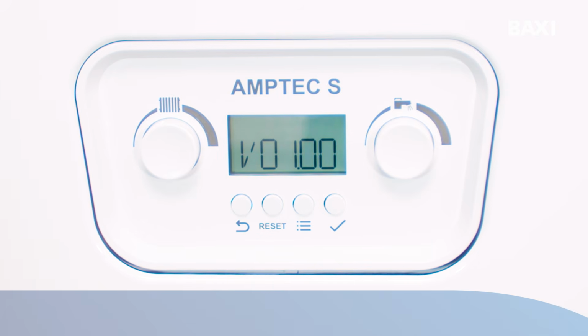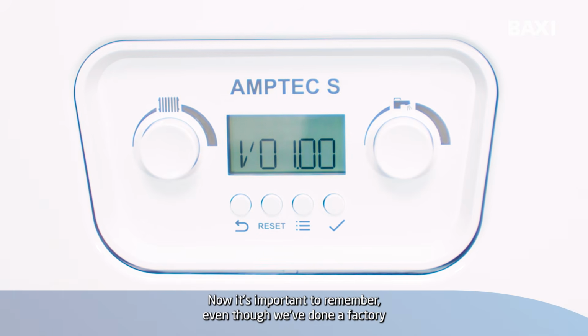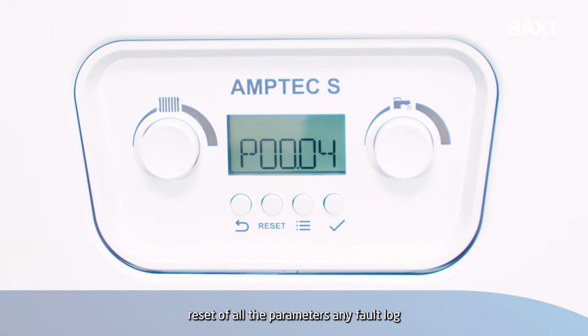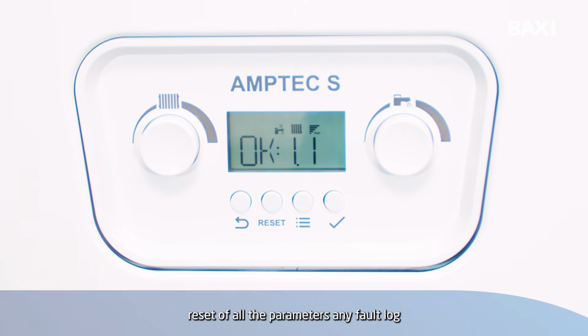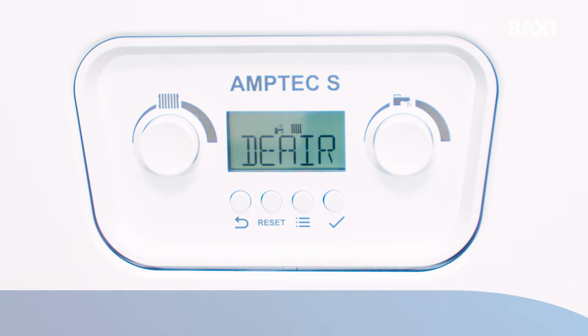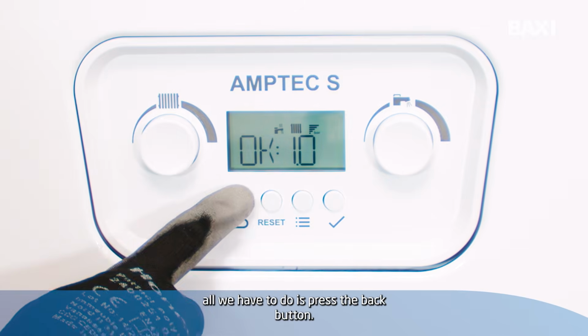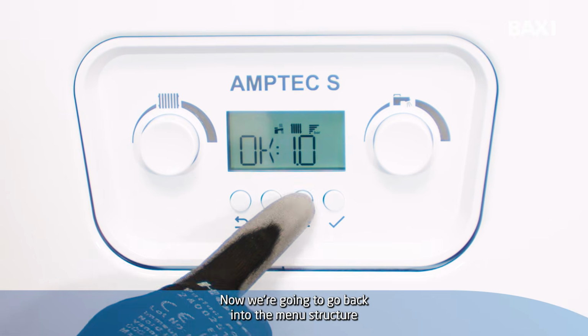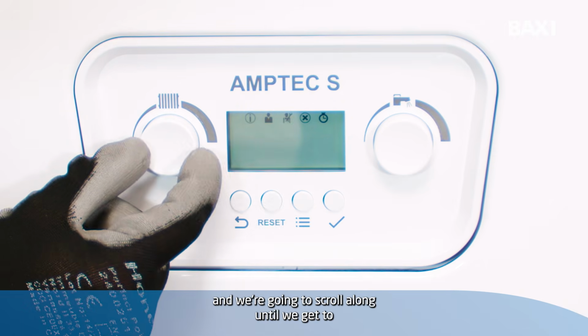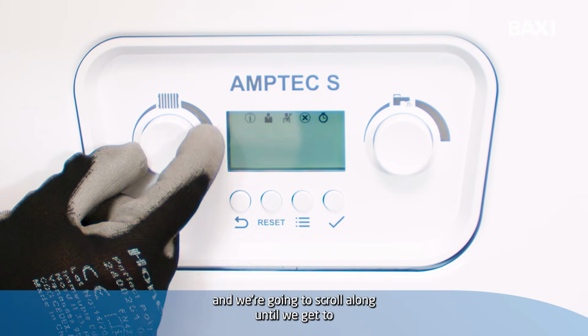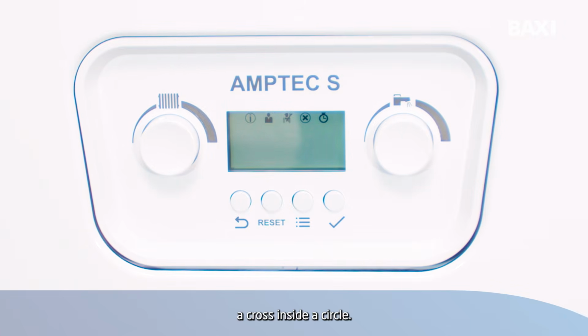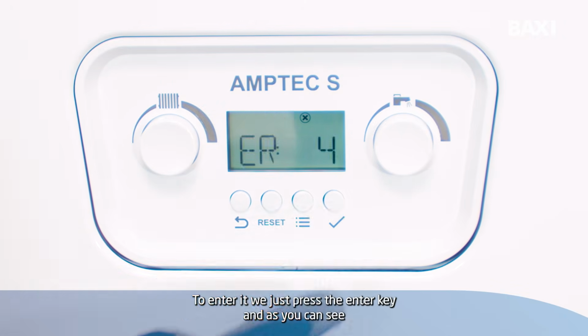factory reset. Now it's important to remember, even though we've done a factory reset of all the parameters, any fault log that was there previously will remain in its history. Now to come back out of that, all we have to do is press the back button. Now we're going to go back into the menu structure and we're going to scroll along till we get to a cross inside a circle. So this is the fault log. To enter it, we just press the enter key.